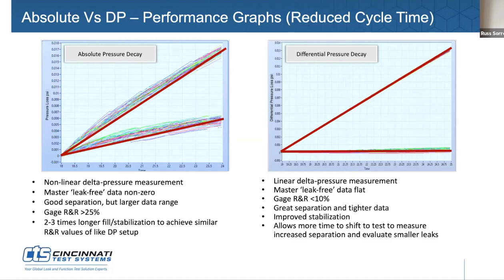With the differential technology, as I look at this, I assume it was the same part that we were thinking. So given the noise, it looks like our number is about 0.016 psi, maybe a little bit higher than that, was the average loss. And then with the differential technology, given that same cycle time, it was about 0.013. So that's a few thousandths of a PSI difference.